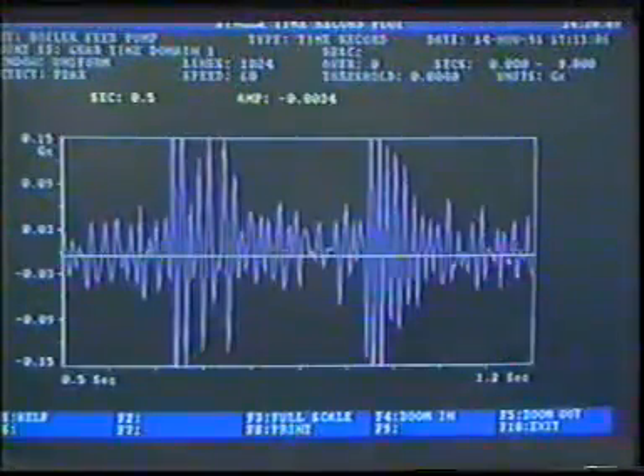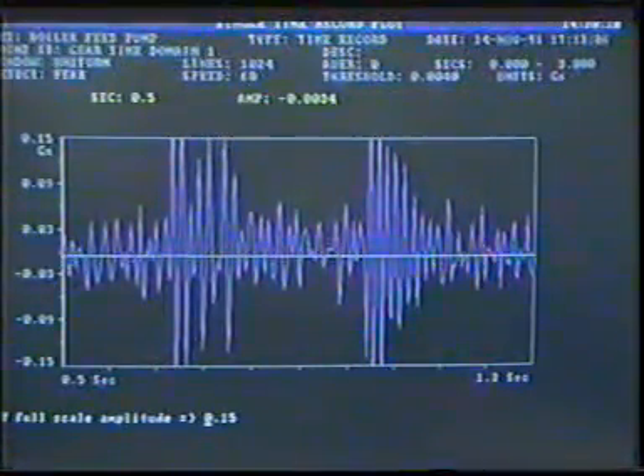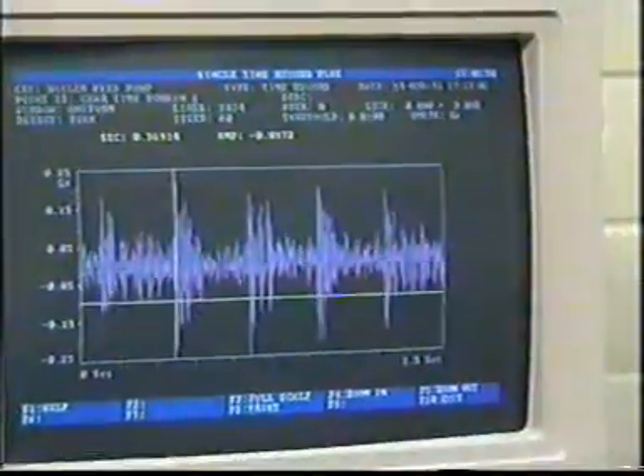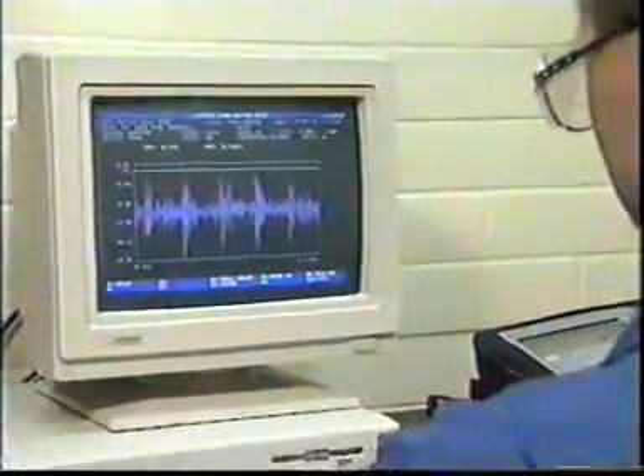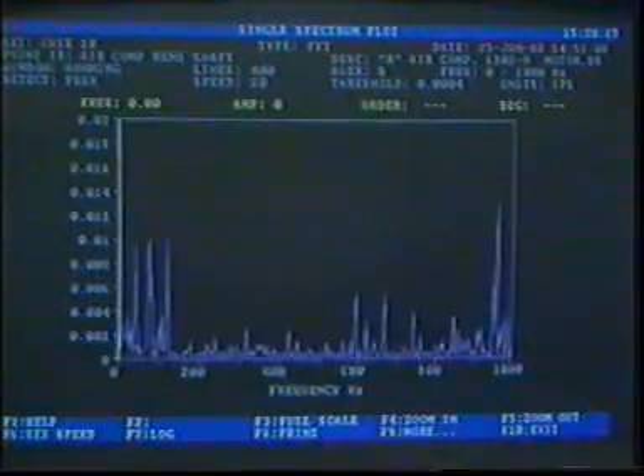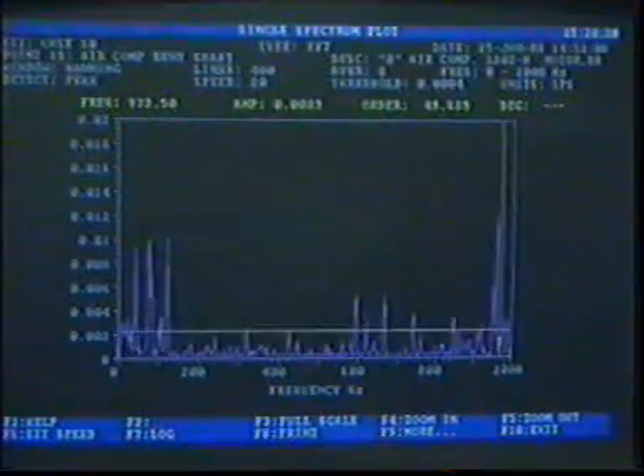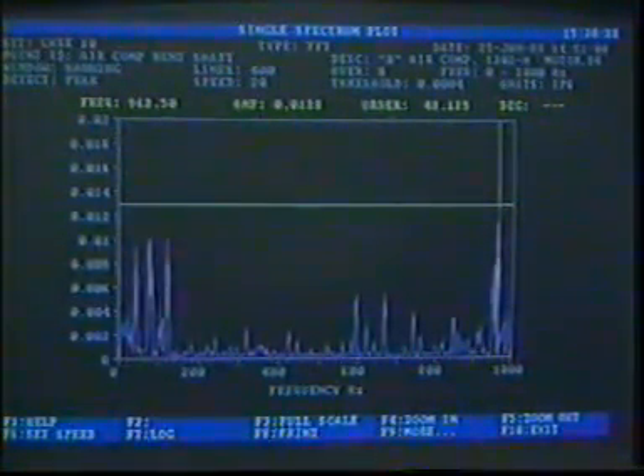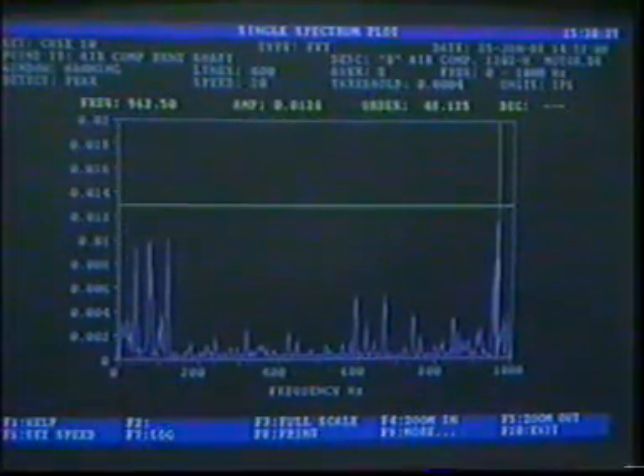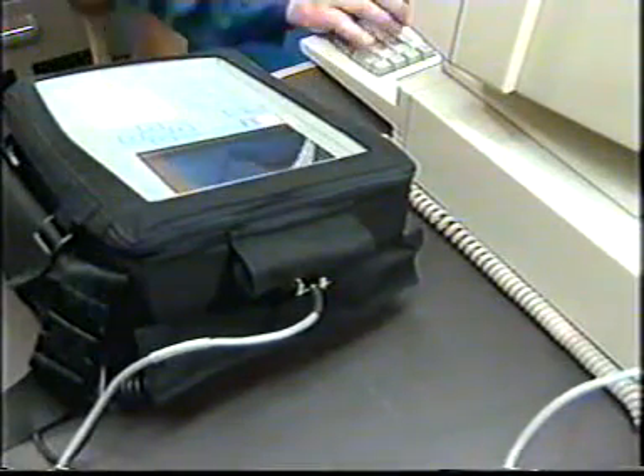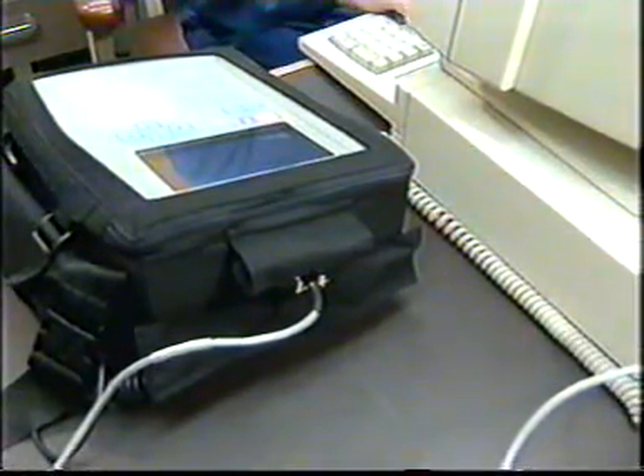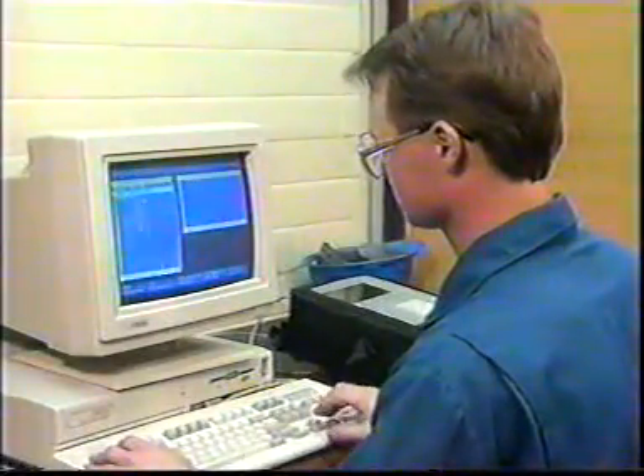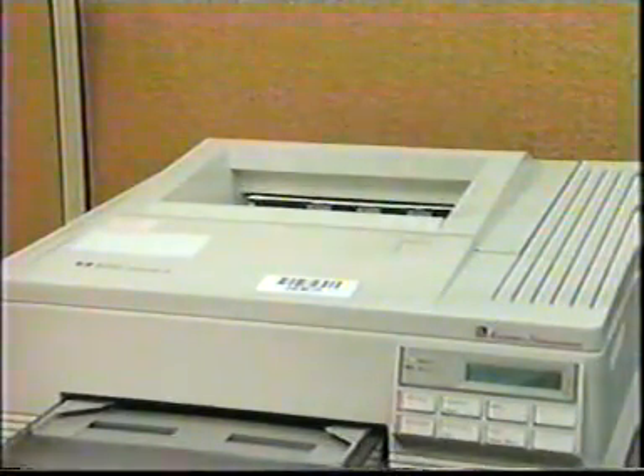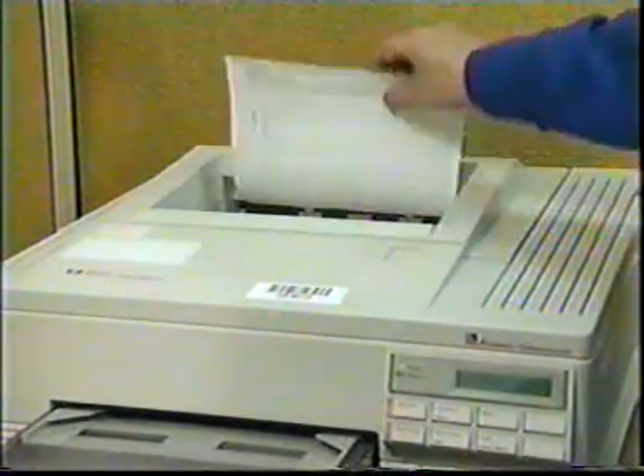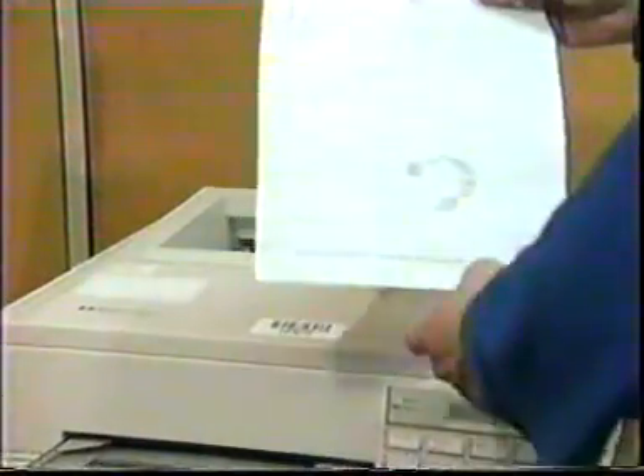The analyzer can expand a portion of the display spectrum. This is called zooming. Zooming is useful for improving resolution, looking at peaks relatively close to each other, and accurately measuring the frequency. Most analyzers have memory storage capability. Several graphs can be compared over time so the technician can see amplitude changes or frequency shifts. Also, data can be transferred to personal computers. There are several programs that perform analysis and show what the points mean, or track and manage vibration data. Data can be printed out when needed by several people or for permanent maintenance records. Some systems provide recorder connections directly on the monitor panel.